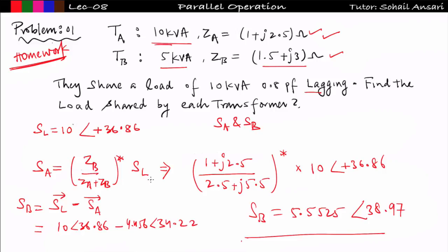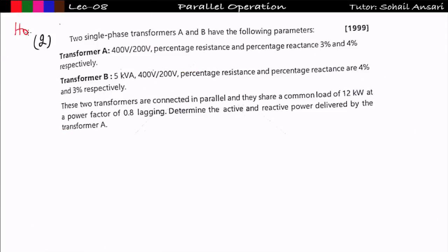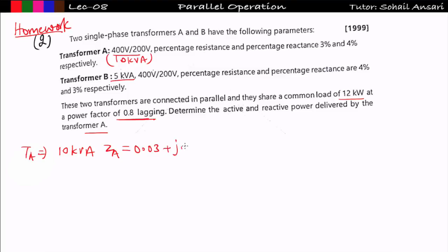Now see the second homework problem. Two single-phase transformers A and B have the following parameters. Transformer A: rating 10 kVA, 400/200 V, resistance per unit 3% and reactance 4%. Transformer B: rating 5 kVA, resistance per unit 4% and reactance 3%. The two transformers are connected in parallel supplying a common load of 12 kilowatts at 0.8 power factor lagging. We need to determine the active and reactive power delivered by transformer A. Here Za = 0.03 + j0.04 pu and Zb = 0.04 + j0.03 pu, both in per unit.